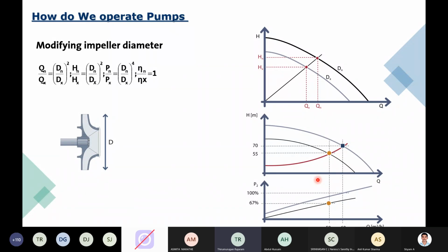New age industries are already into that and trying to accommodate it, because they can optimize at the initial level itself. Whereas if you find a pump which is quite old and you want to reduce the flow unnecessarily, which is not required for the site condition, there is also one method you can do: trimming your impeller, because the impeller is the component that is designed to generate the required flow and head. So once you trim this impeller, you are trimming its diameter.